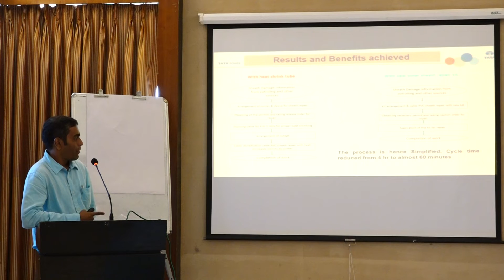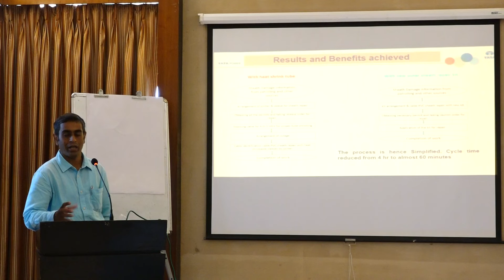One more advantage is that your cycle time is reduced. In this you can see, earlier we required 4 to 5 hours to repair with that kit, because you need to take an outage on that cable. You cannot work directly on a cable which is charged. So you need to take an outage. You have to identify the cable. Then you can repair with that heat shrink kit. But with the cold shrink kit, you don't need an outage. You just simply need to wrap that paper, and it becomes so hard that there is no chance of water ingress in that.